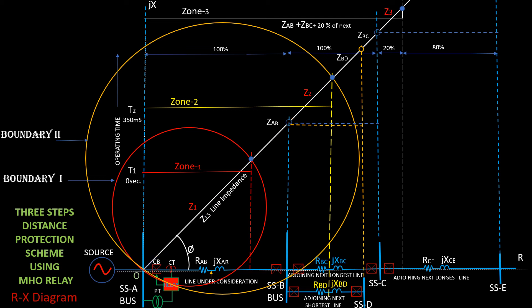Z3, the calculated impedance of the protected zone 3. Zone 3 relay will operate when relay measures impedance falls within the zone 3 boundary circle. Time of operation is 700 millisecond.